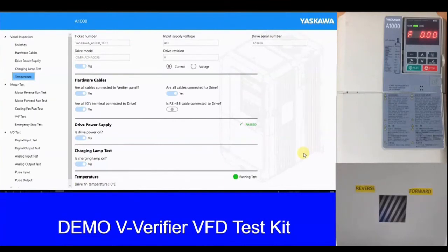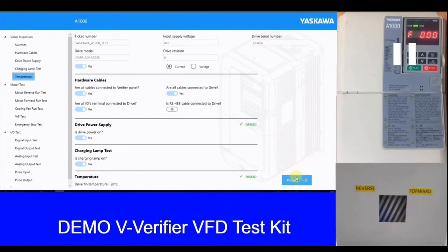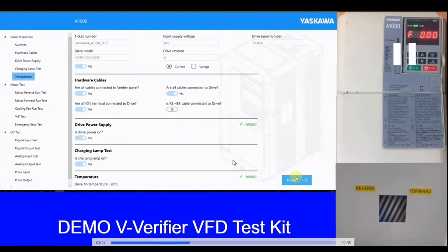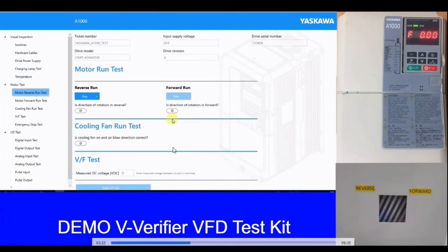Once the charging lamp LED test is complete, we go ahead with the temperature test. In idle conditions or room temperature environment, it is recommended that the temperature of the VFD be below 40 degrees Celsius. Right now it is 28 degrees as measured from this particular drive, so that is a pass.